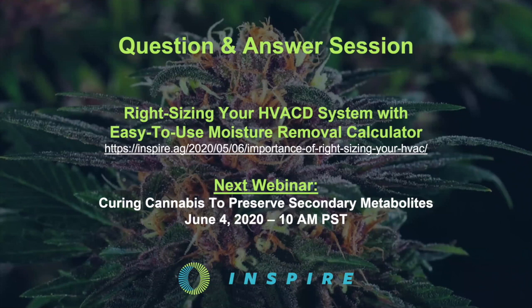Boy, you just threw me a soft one there, I guess. You know, at InSpire, we've designed and built some very efficient ways to dehumidify the air. The challenge is one of being able to use the energy you're putting into the system in a novel way. In standard dehumidification systems, they do that by using compressor energy to reheat the air after they've cooled it to that temperature where you get all the moisture out.